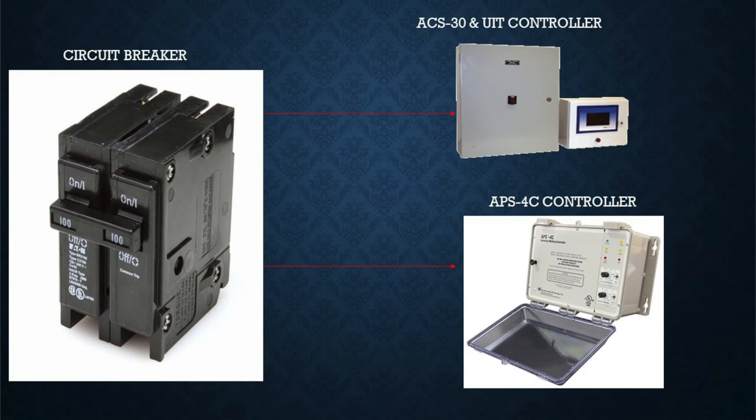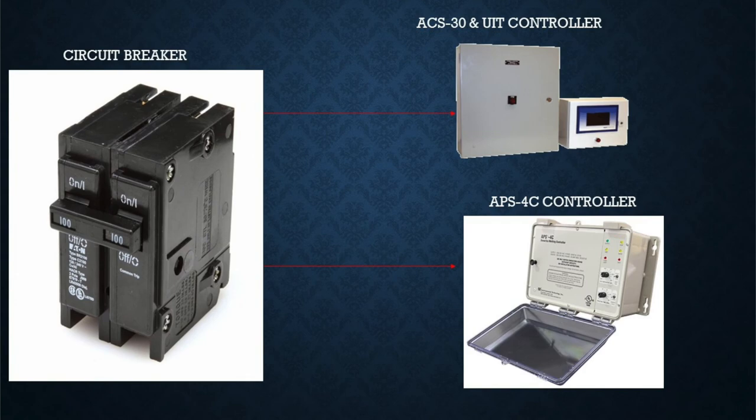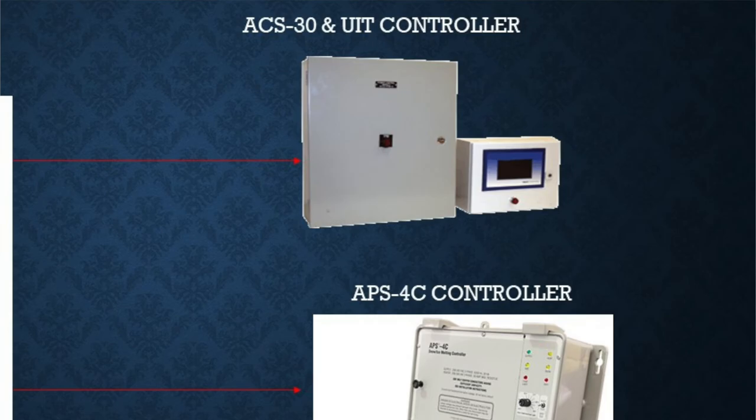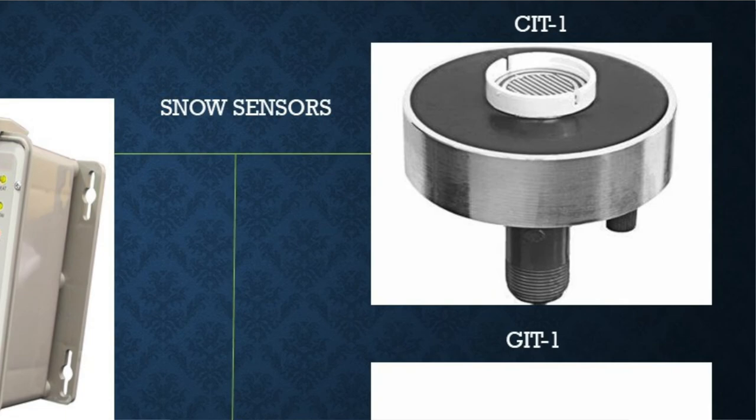The basic setup of a roof and gutter system is similar to a regular pipe system. First you have power distribution — a circuit breaker. From the breaker you have a controller, such as a snowmelt controller or an ACS-30 system from previous videos. The controller is energized when a signal is sent from the snowmelt sensors. There are two sensors: the first is a CIT, a snowmelt sensor mounted on or near the roof.